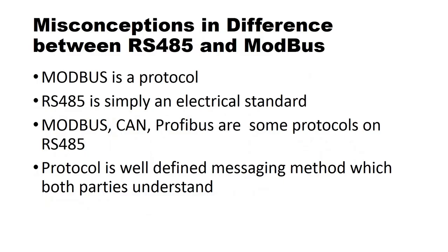Now, one of the misconceptions which many people have is that RS485 and Modbus are the same. No, RS485 is simply an electrical standard. Modbus is one of the protocols over RS485. There are other protocols like Modbus, CAN, Profibus, etc., which are also well-defined messaging methods which both the parties understand.